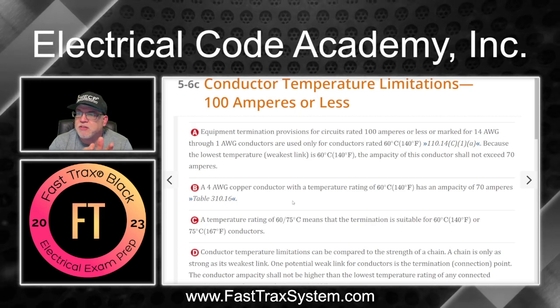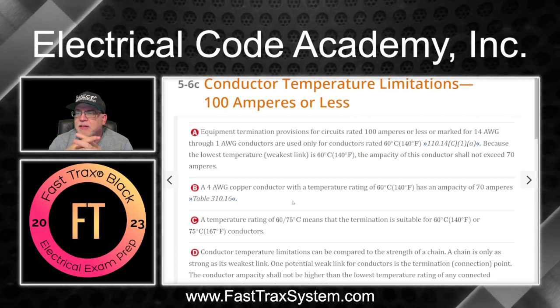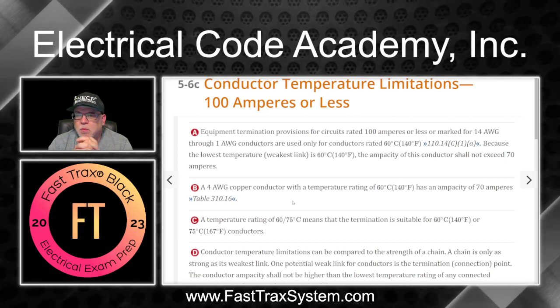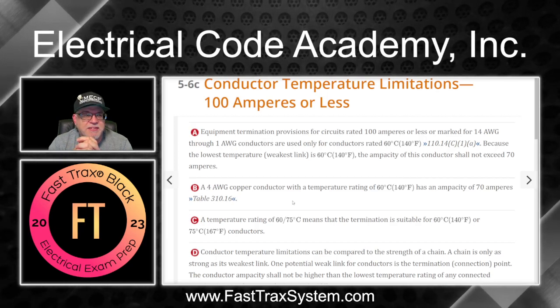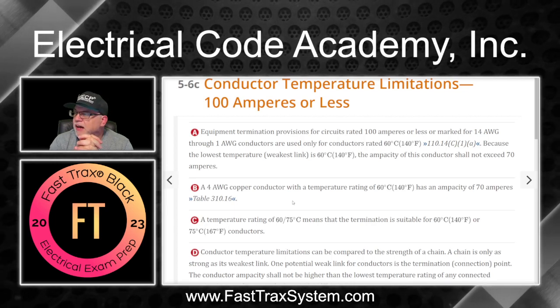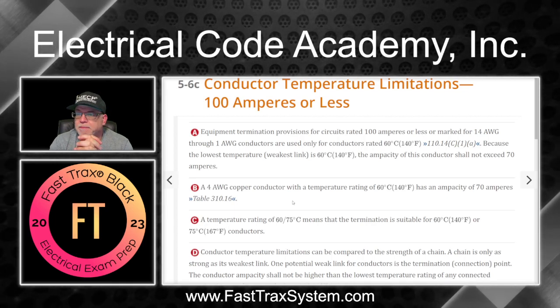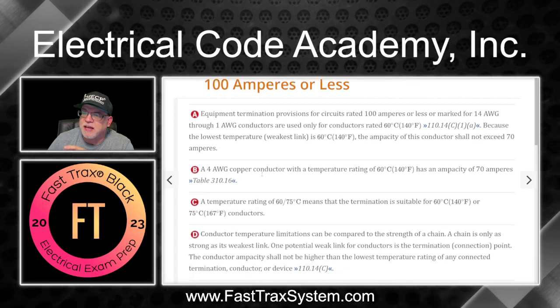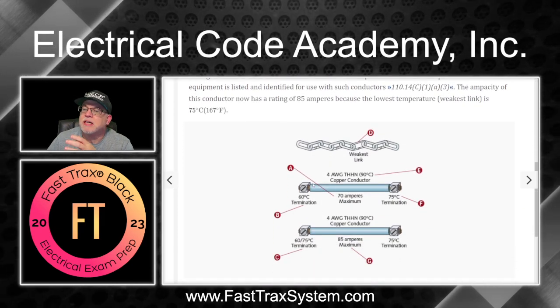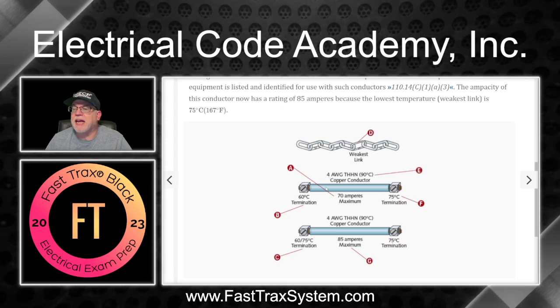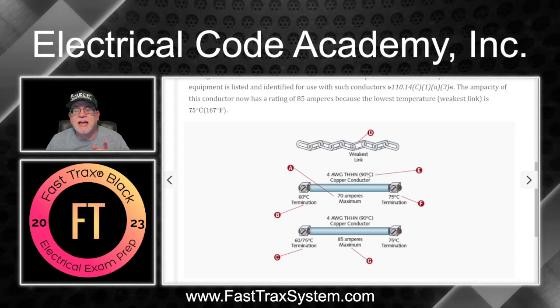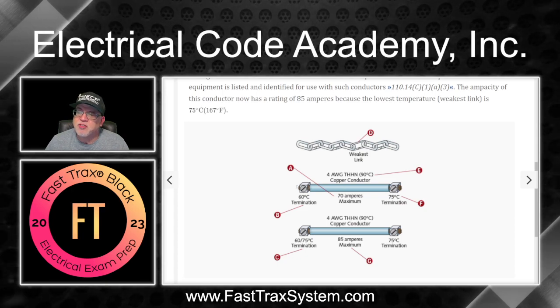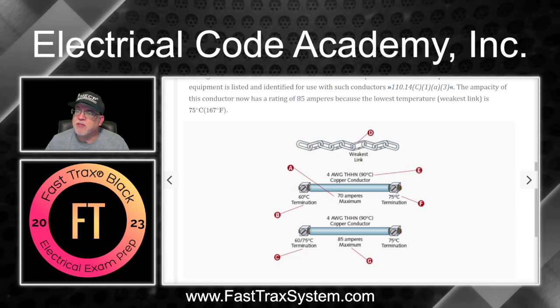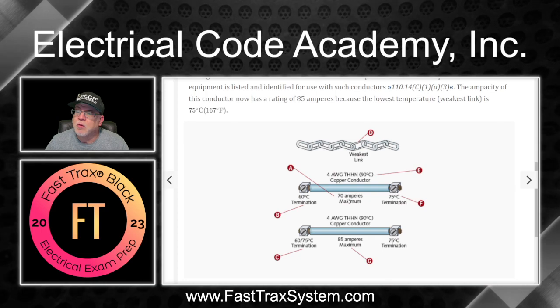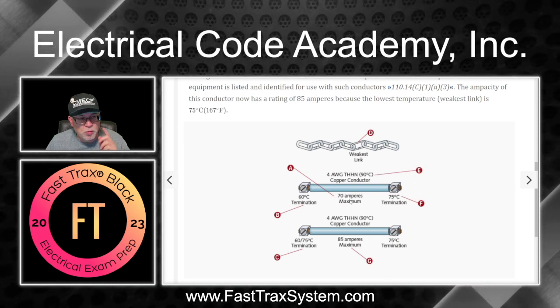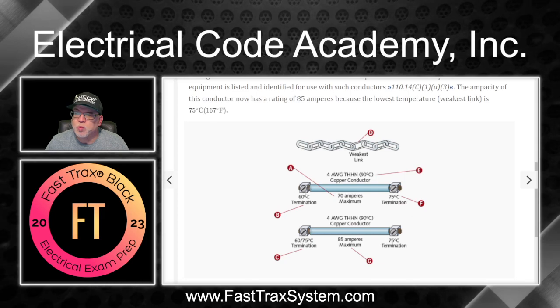That is based on what we have in 310.16, so we can verify that in the code. But the reason it says 70 amps here is because you would go down and look at our example, which is dealing with a 4-gauge THHN that is rated 90. But since this terminal is rated 60, even if this one's rated 75, the maximum is going to be 70. Why? Because of this weak link right here.